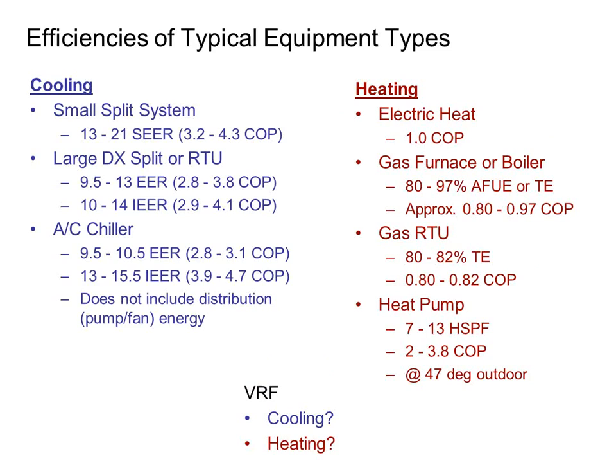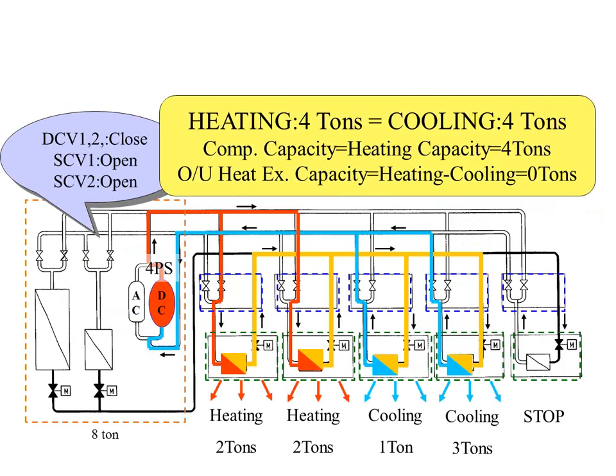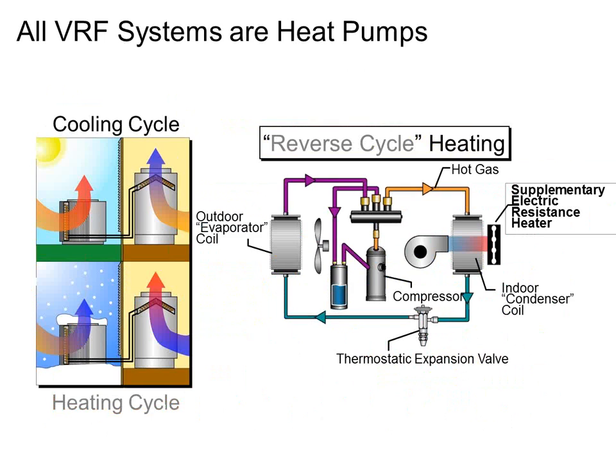Now, a couple folks, you guys are typing in that you can't have anything above 100% efficient. That is completely and totally not true. You can definitely be above 100% efficient. And I will try to go back real quick and explain, just only because there's so many guys asking. I thought we could skip the VRF 101, but maybe we need just one more topic on it. When I am using a gas furnace or a boiler to heat your building or your home, or a rooftop unit for that matter, a gas-fired piece of equipment, I am burning a fuel to make heat. And some of that heat goes up the stack, goes up the flue, right? So those products that burn gas are never 100% efficient, unless you have a direct-fired piece of equipment with no ventilation air, in which case you probably die soon, right? But they're never more than 100% efficient.